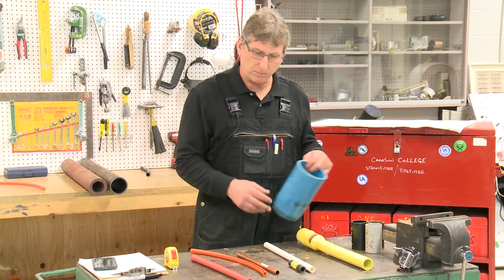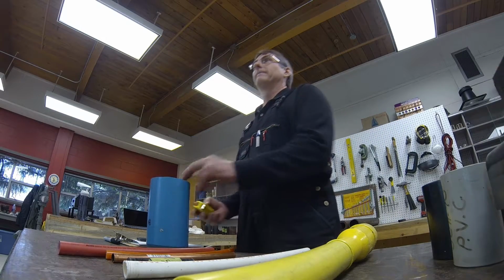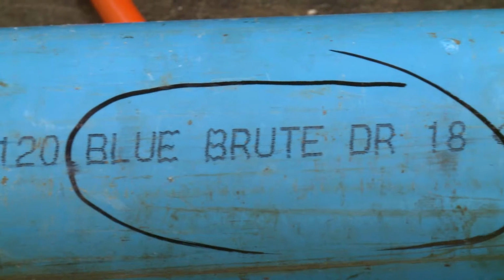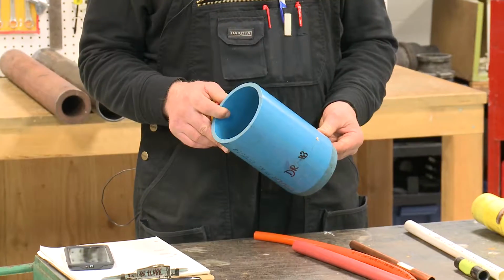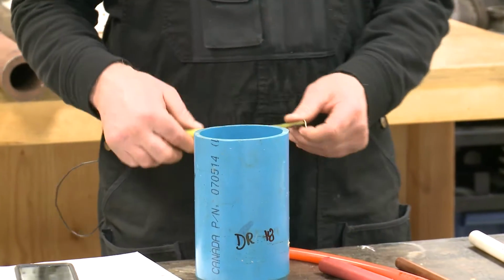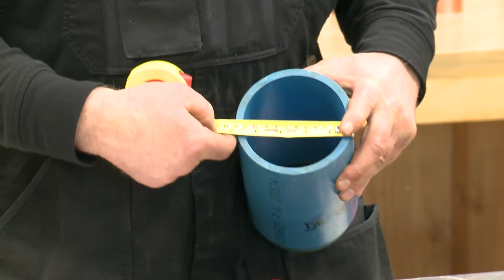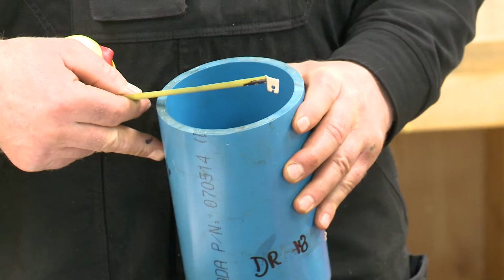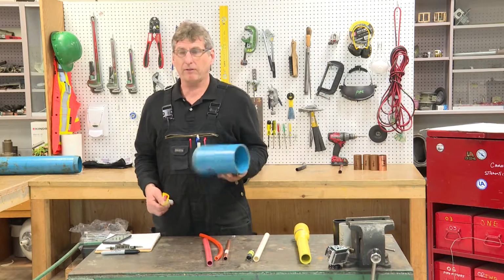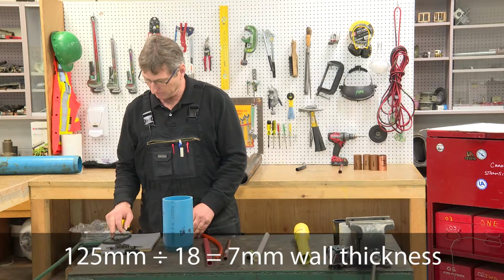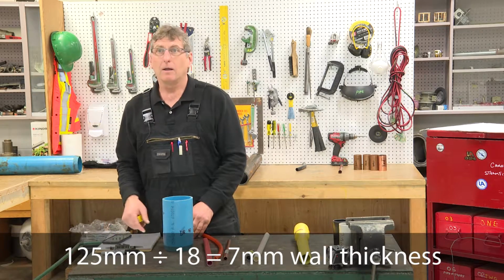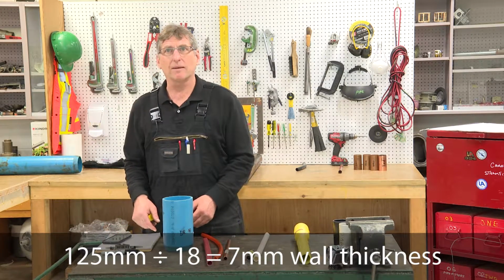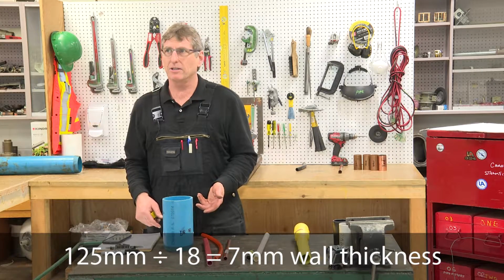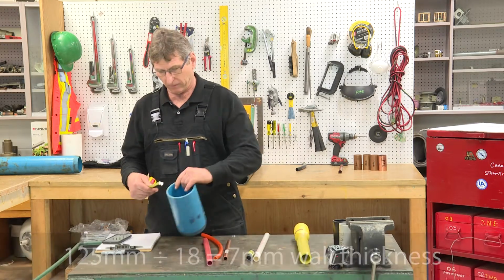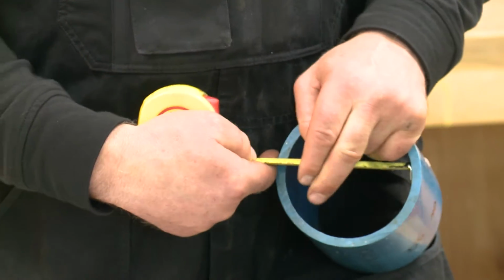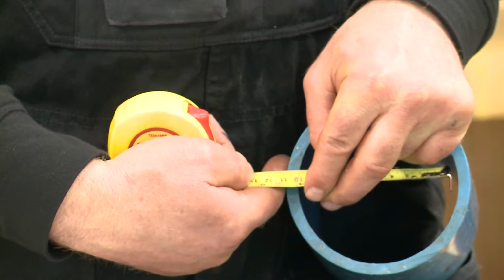Here's a piece of 6-inch PVC. It's used for water mains. It's got a DR rating of 18. When we measure the outside diameter, we get 125 millimeters. Now, if we divide that by 18, it comes out to just under 7. So that means that the approximate wall thickness is 7 millimeters. If we check that, we'd find it to be true. We're at 7 millimeters.